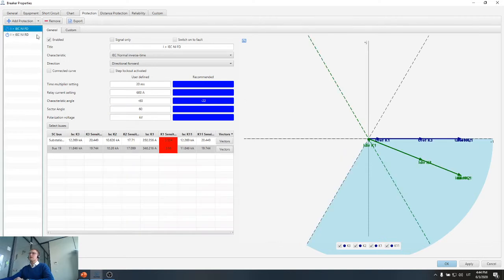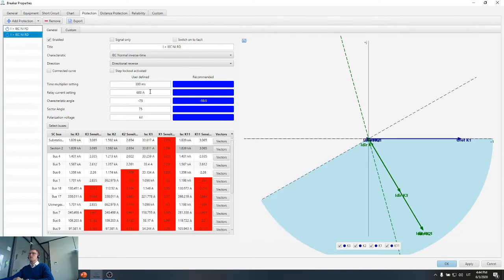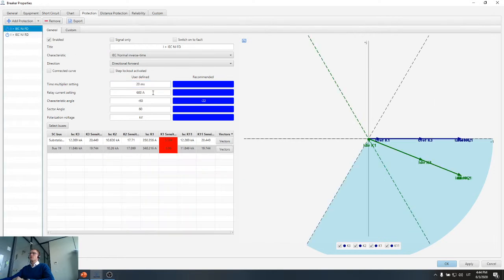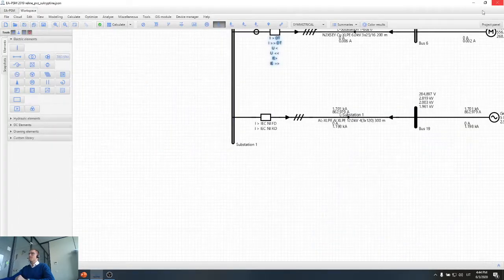So the difference is that the directional forward relay is tripping in minimum time, which is 20 milliseconds, and the directional reverse protection device is tripping in 300 milliseconds, because we need to also maintain selectivity with other protection devices. However, the forward direction protection device does not have to maintain selectivity with other protection devices, therefore time here is minimum.